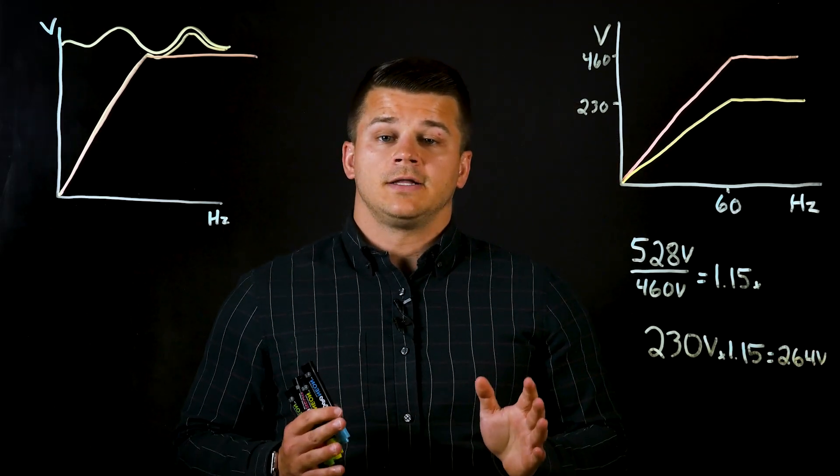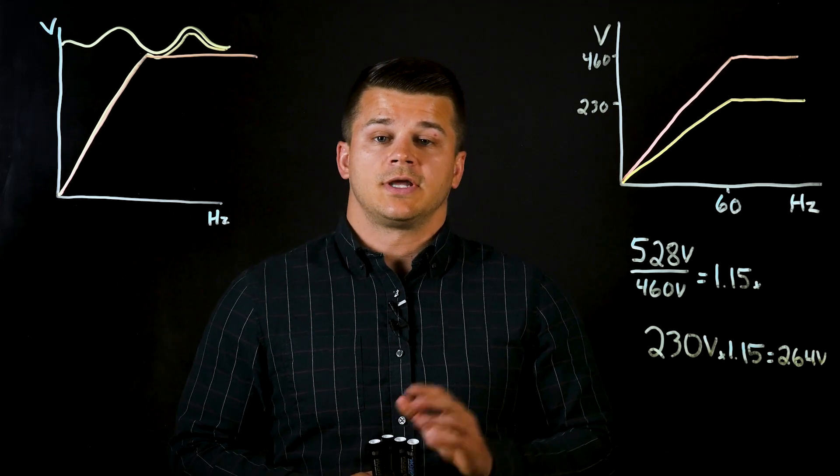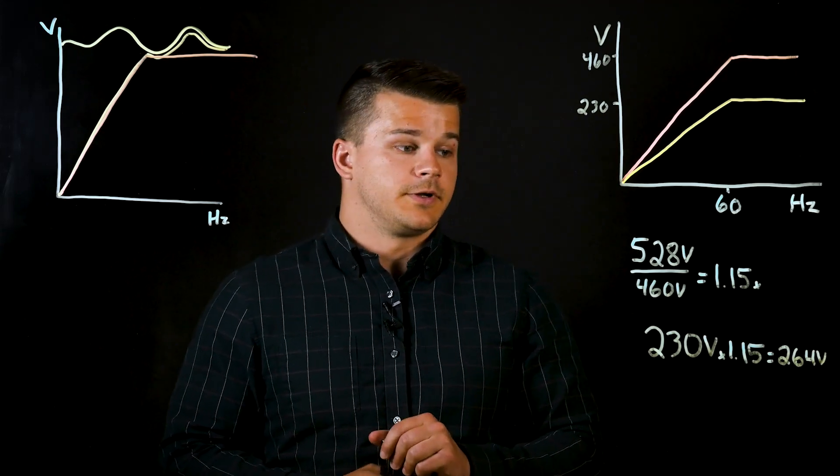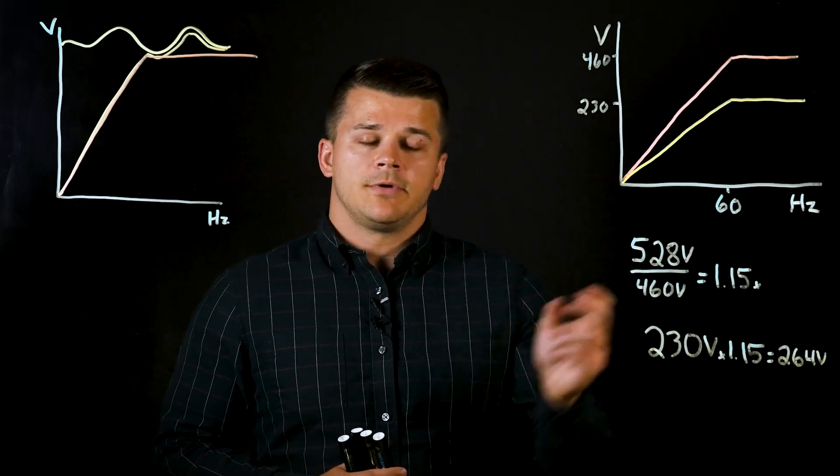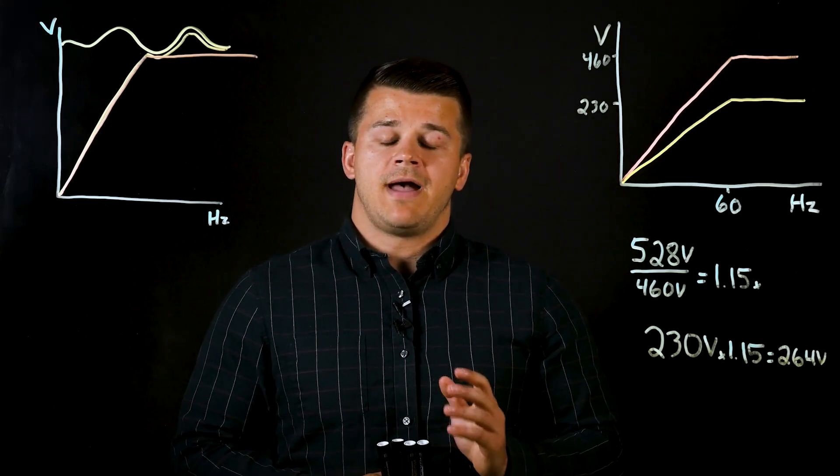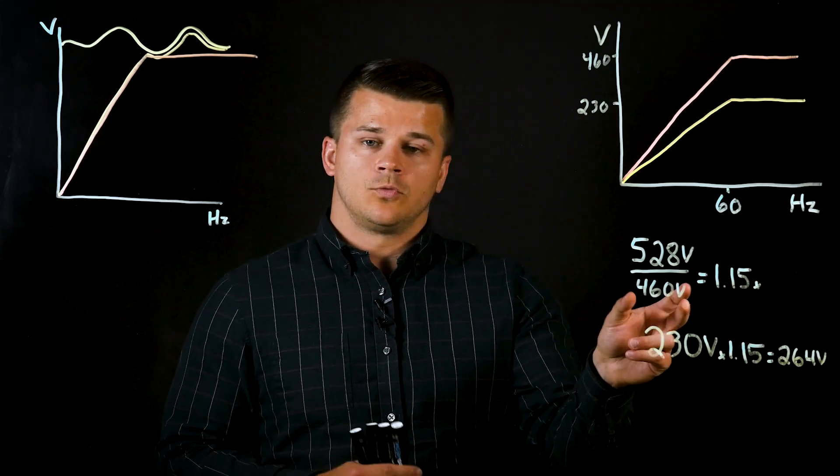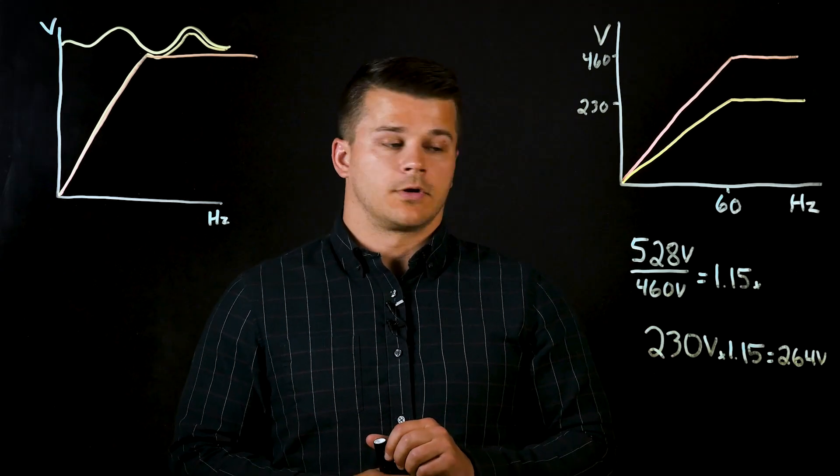So now to highlight how the voltage stabilization can affect the output voltage to the motor, we'll get into the numbers behind the theory. This top number here, the 528 volts, is the max allowable input voltage to the KEB drive, and the 460 volts would be a typical rated voltage for a motor.